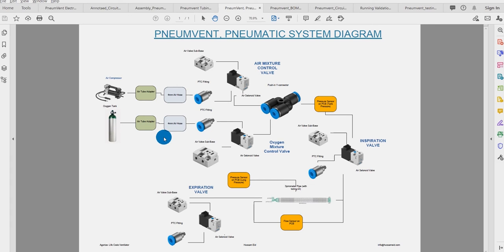Now, if we take a look at the pneumatic system, I went through it. I just want to mention that we have this document describing how the system is connected from a pneumatic point of view. We have a Y connector here that essentially combines the oxygen and the air compressor air, and this is always regulated. So I can always control how much air is flowing into the Y tube, as well as how much oxygen, using the MCU, because I am always in constant feedback of how much pressure I'm allowing to go through and how much pressure I can tolerate.